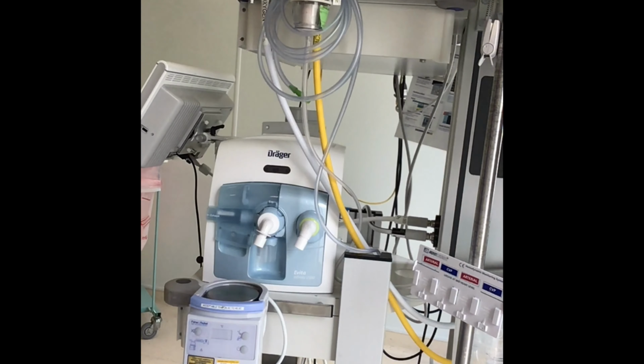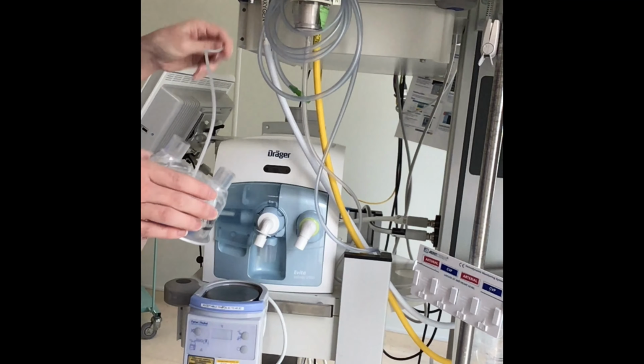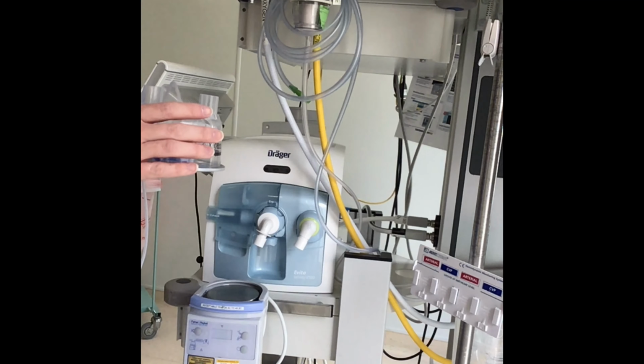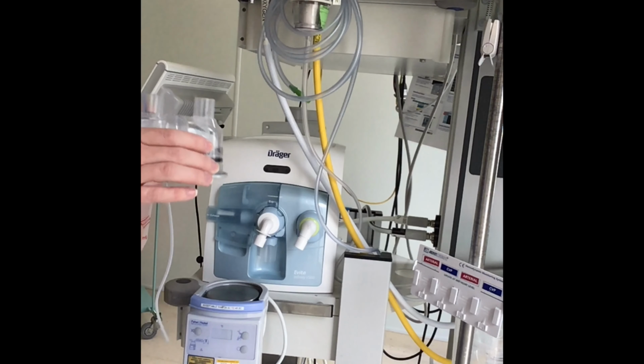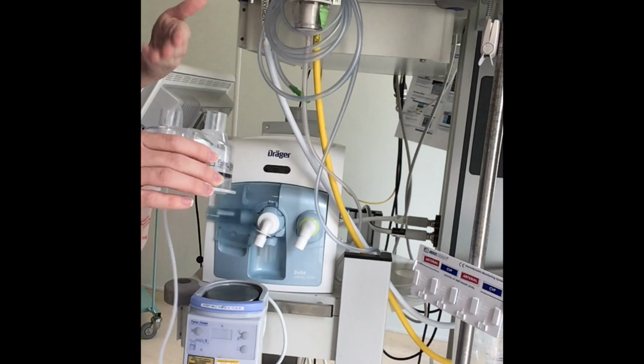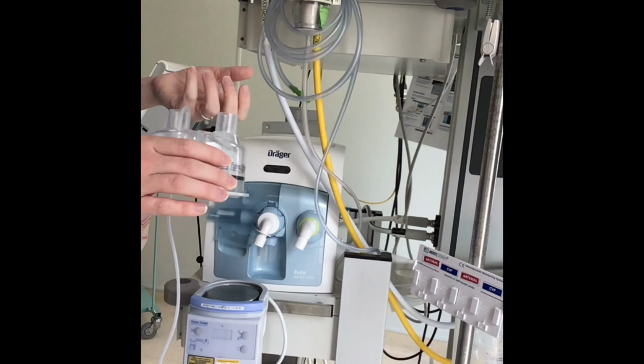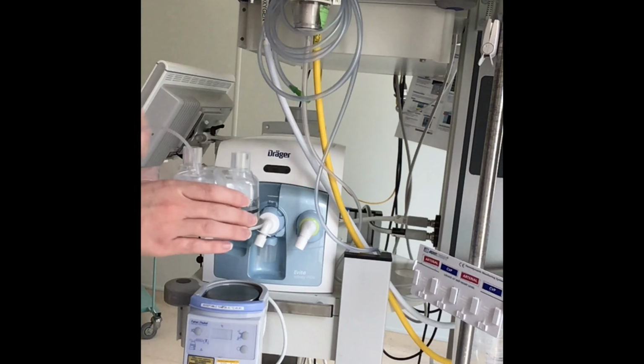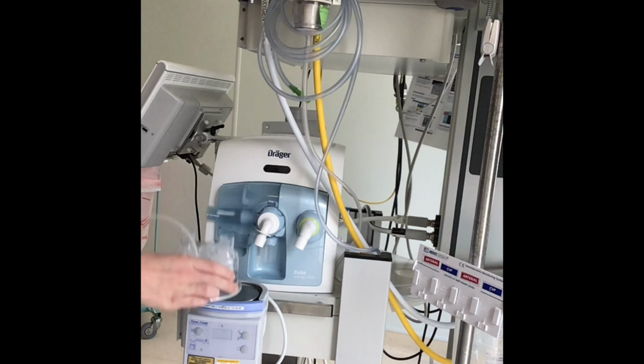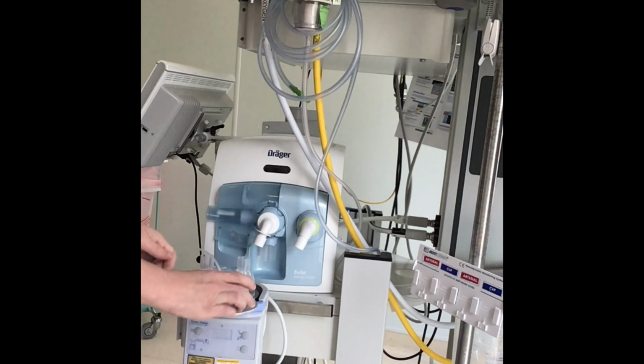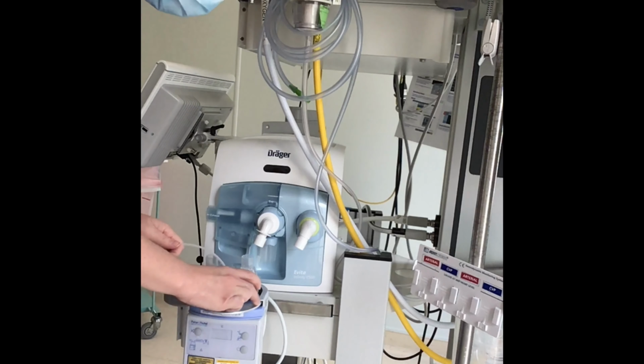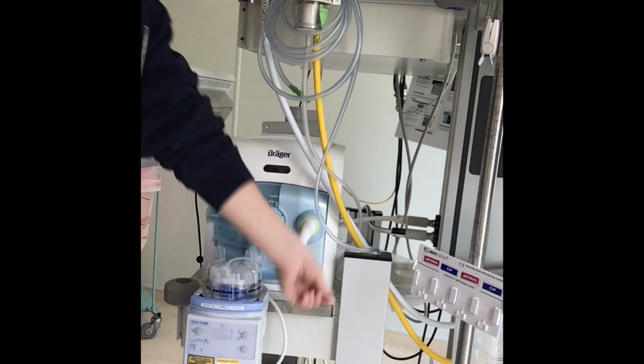Connecting the humidified circuit, it's really important when you take everything out of the packet that you don't actually spike the water until you've put the tubing through its checks, because if not it's going to fail. So keep everything sealed until you've actually put the ventilator through its checks and it's passed, and then you can spike your bag. I'm going to connect the water bath to the heater, so push down on the blue bit and it will slide on until it clicks.